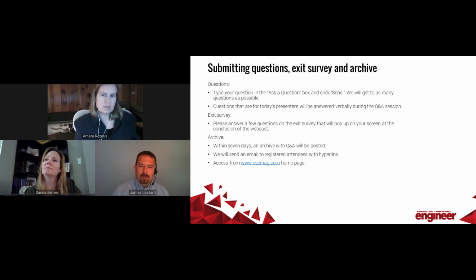Good question. Yeah, so if you have NEC 700 emergency loads or NEC 701 legally required loads, there's a very specific requirement about the duration of outage from when the utility fails to when the generator picks up those loads. There's a certain window that's defined. For emergency, it's 10 seconds. In those cases, you need an automatic transfer switch to make that transition in that short duration. If you have optional standby loads, you can put those on a manual transfer because there may be instances where it's of lower priority. And if you have capacity on the generator, you can choose to manually transfer it onto the generator system once all the other ATSs have brought the required loads on board.